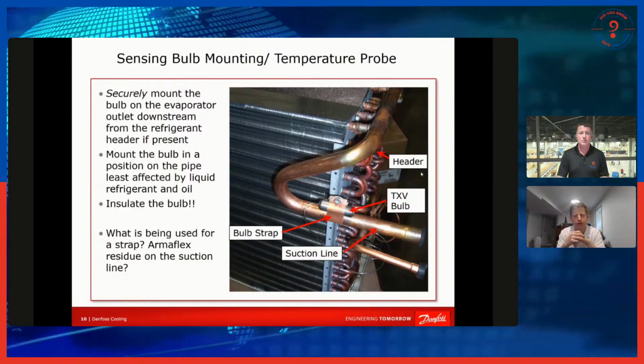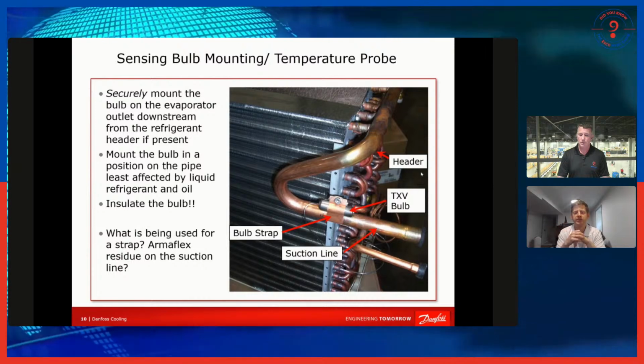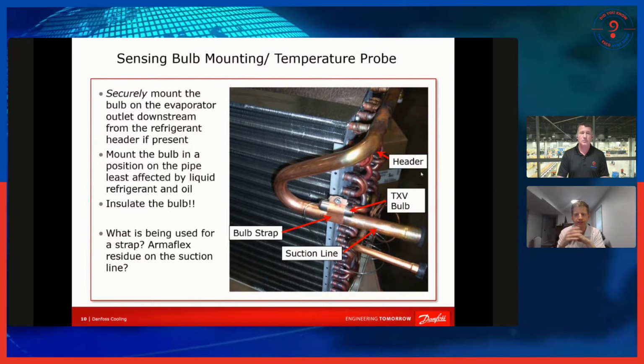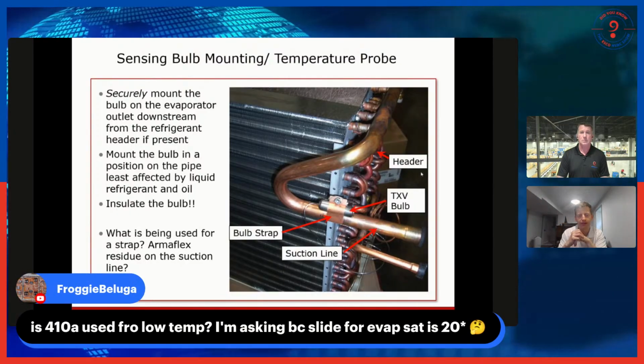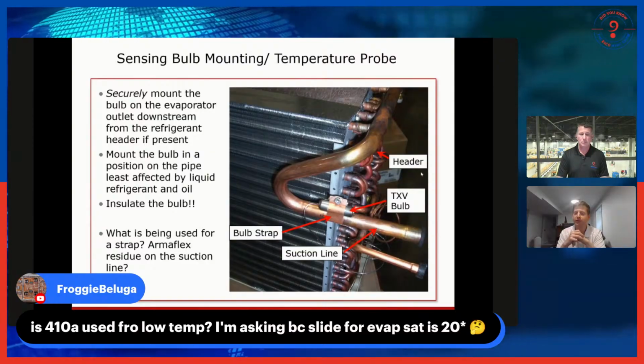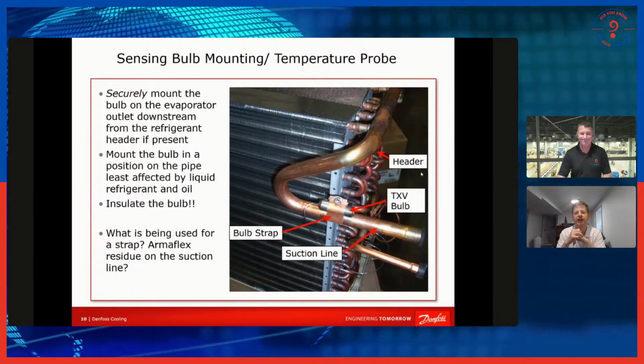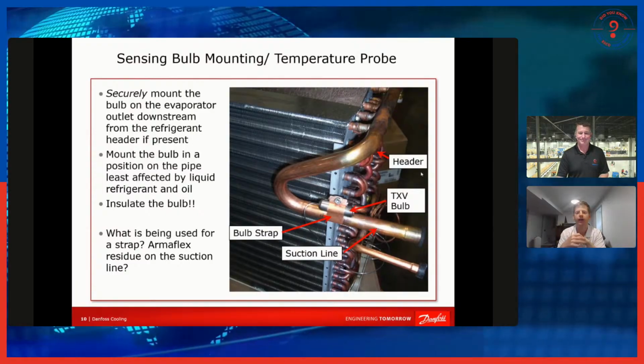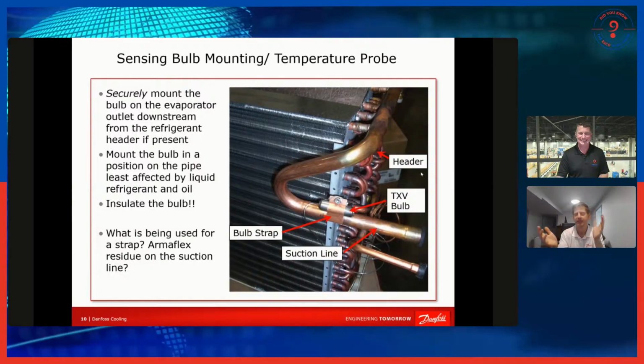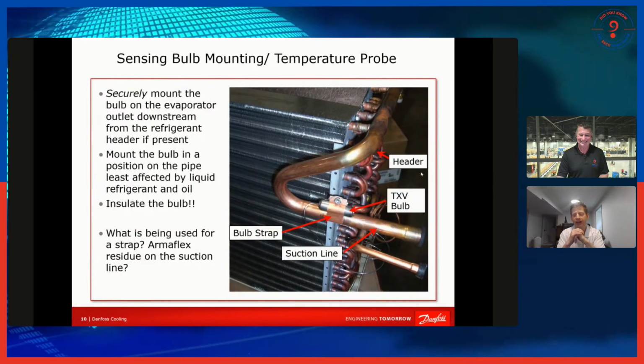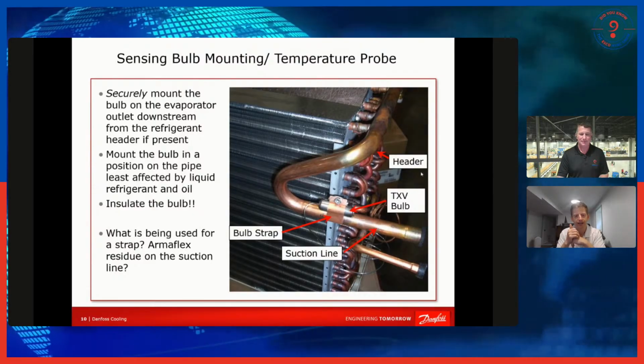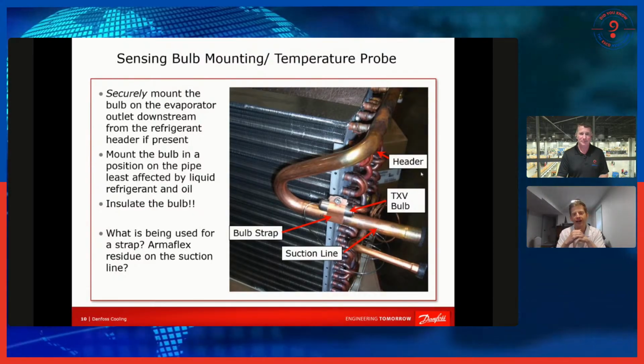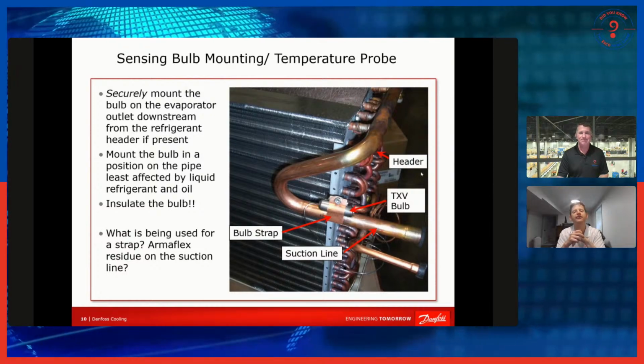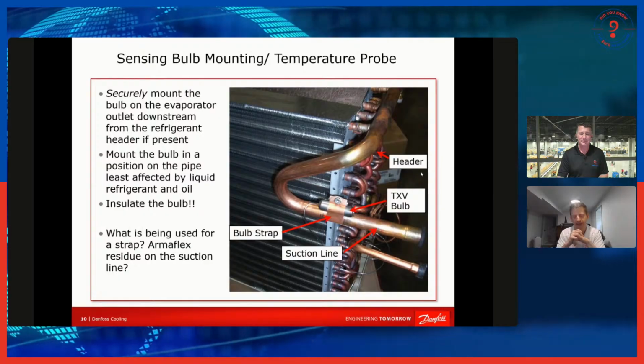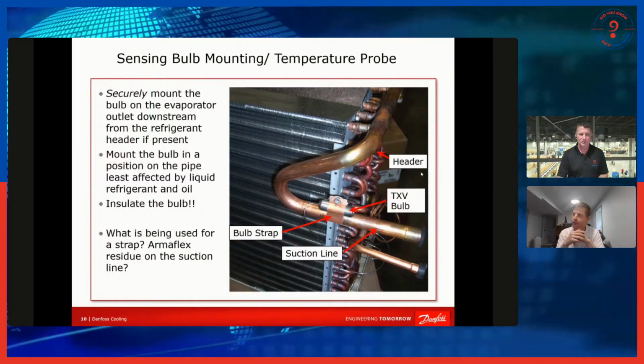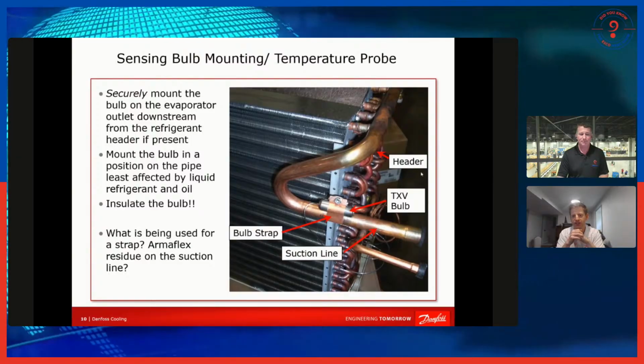I myself noticed a question over there on the side that I can answer. Someone was saying, is 410A used for low temperature? They're asking because in the slide I had up, there was a 20-degree evaporator temperature. And actually, sometimes 410A is used in ice machines. There are some lines of ice machines, like the one you'd find in a hotel. I don't know why there are so many ice machines in hotels, but anyway, that's the example I like to go with. There are certain manufacturers that use 410A for that, and I don't have a good answer as to why. I was not involved in the designs, but you can find it in ice machine applications. So I assume whoever made that slide made it for an ice machine situation.